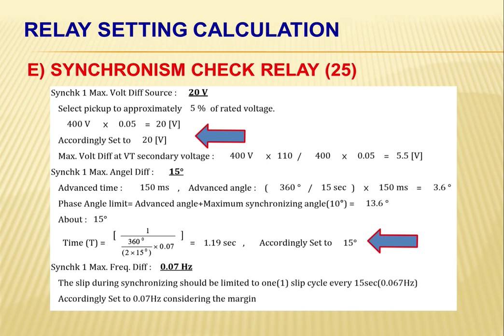And for our maximum frequency difference, if one source has a slightly higher frequency, the sources may come to perfect synchronization for a brief time and then slip away into not being synchronized. If two sources with different frequencies are close, real power or watts flow between the sources, which will vary depending on the relative phase angle difference between the waves. Since the frequency of one source is slightly ahead, the phase angle keeps changing throughout, and hence the real power also keeps changing.